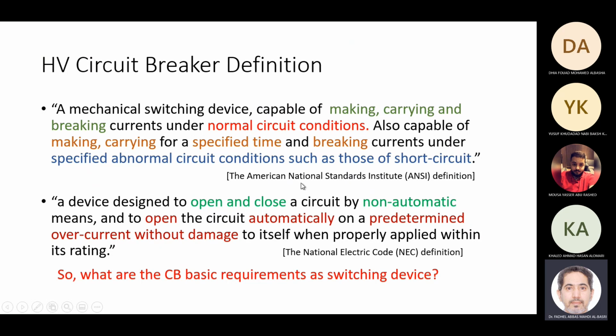According to ANSI, the American National Standards Institute, this is the definition: a mechanical switching device able to make, meaning it can close into, carry continuously, and break a current under normal operating conditions, which is load conditions, no fault conditions. When I say make, it means I can close. Carry means when it is in a closed position, it can carry this current continuously. And break means when you open it. So it can make, carry, and break a normal current, but it is also capable of making, carrying, and breaking a short circuit current, carrying for a specified time.